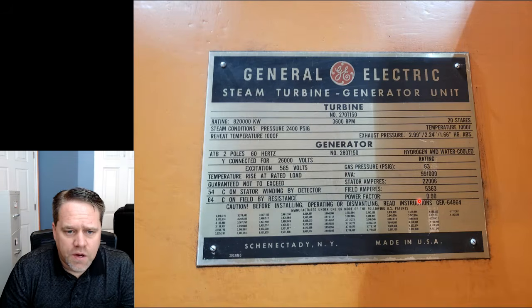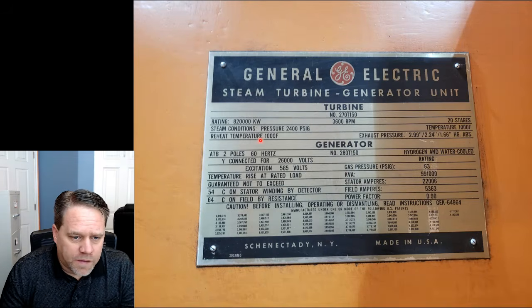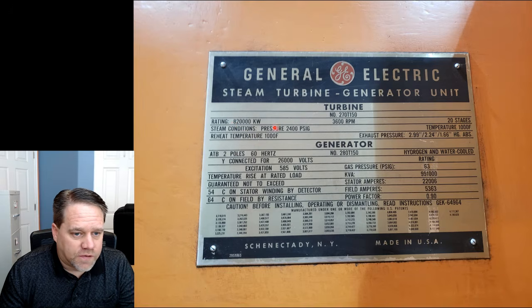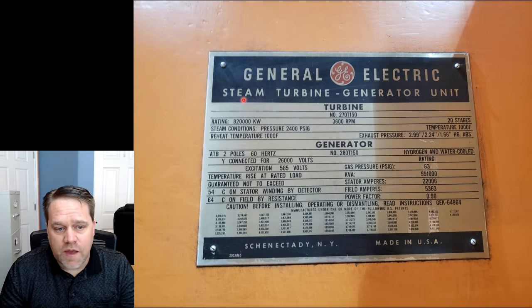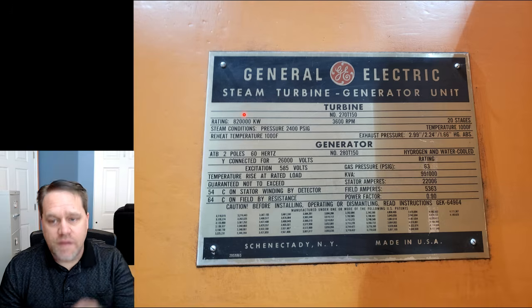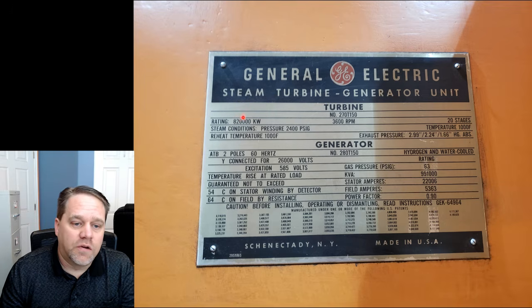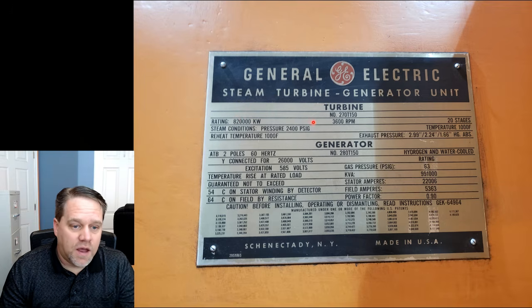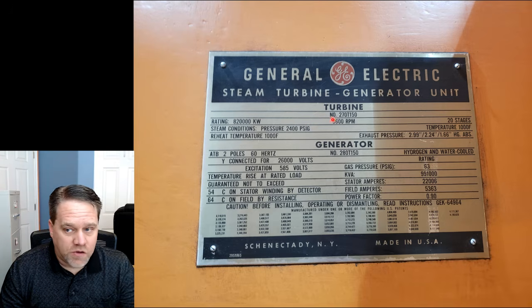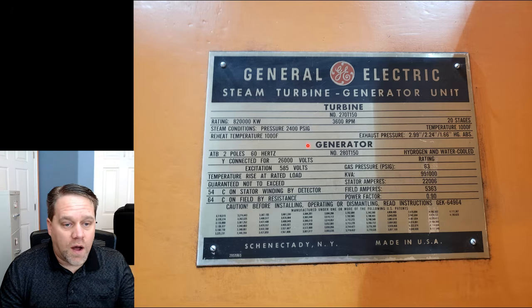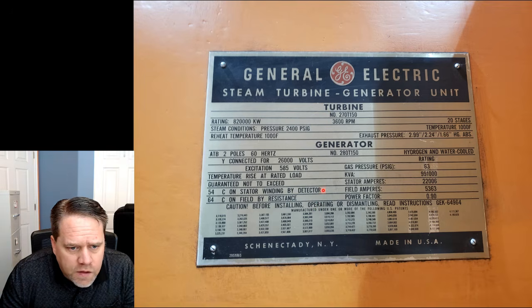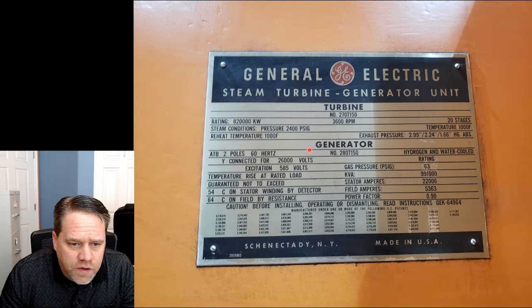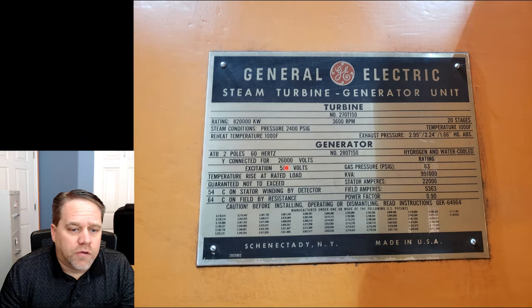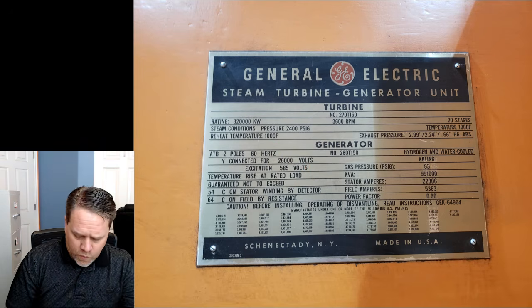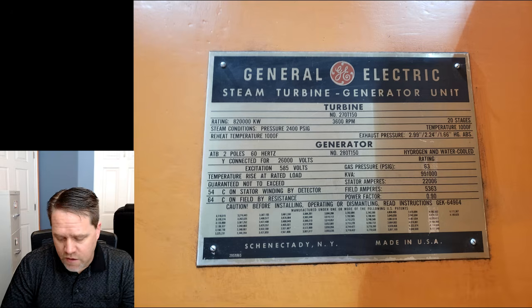The nameplate on this guy is, well, it's one of those numbers where I have to check myself and make sure I'm even saying it right. It's 820,000 kW, or 820 megawatts. Just under a billion watts. And the voltage output is 26,000 volts, three-phase. So 26,000 volts times 1.732 is about 45,000.